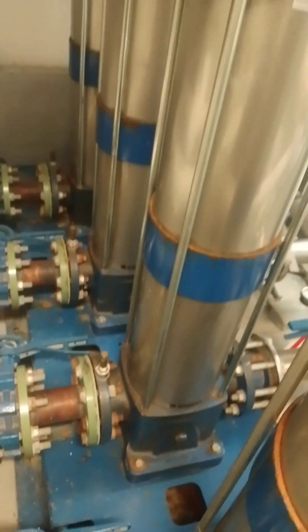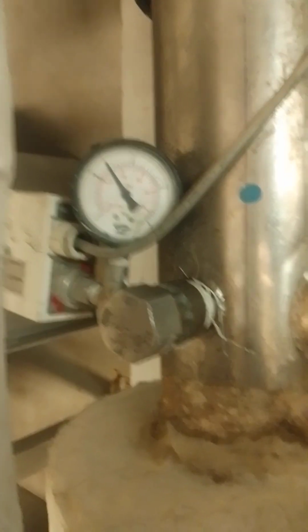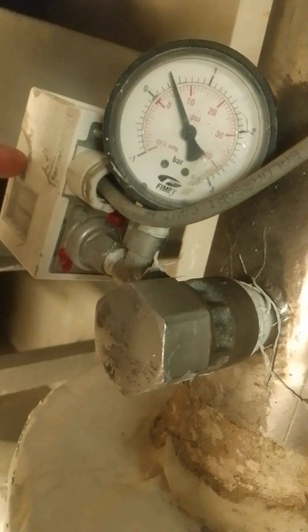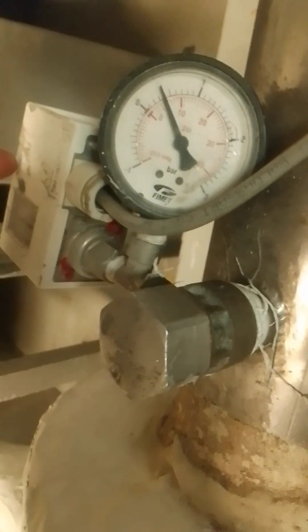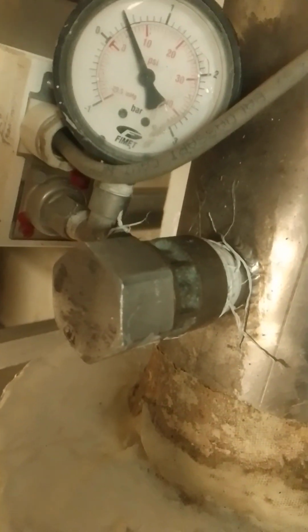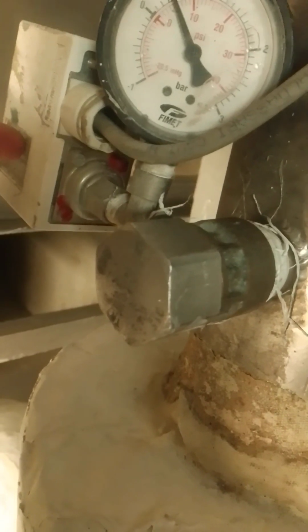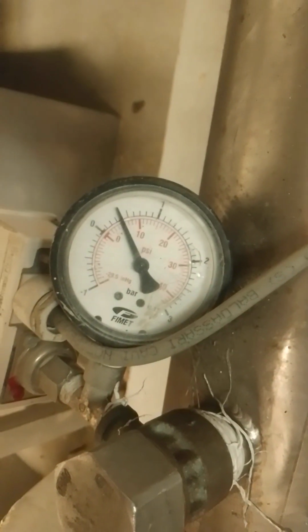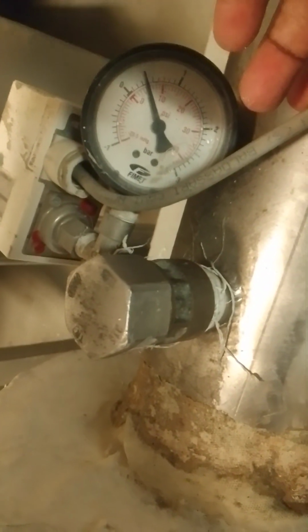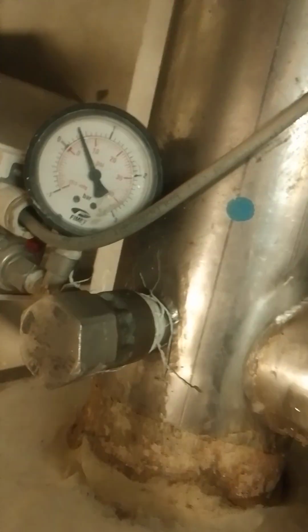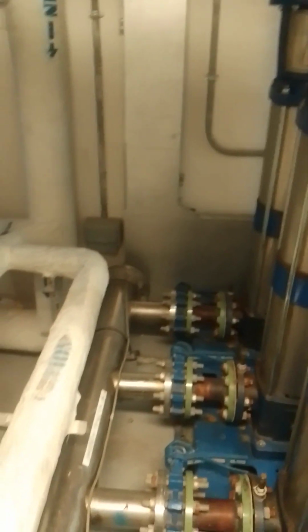I told you there is a pressure switch. This is a pressure switch. We call it pressure switch. It's electrically controlled by the pressure of water according to the demand. You can see this is a pressure meter. So this pressure switch is the one which sends the command to the relay. Then the relay sends command to the contactor to start or to switch off the system.